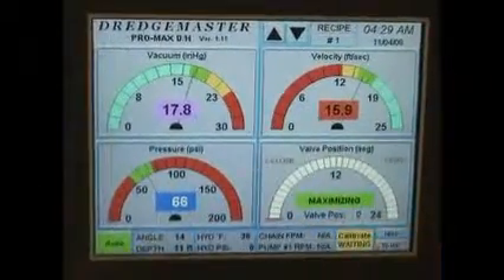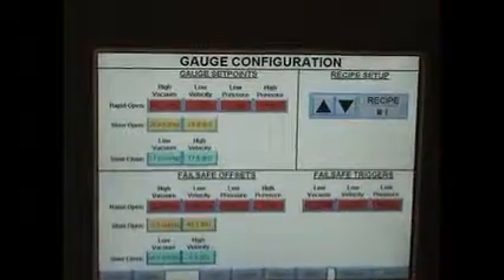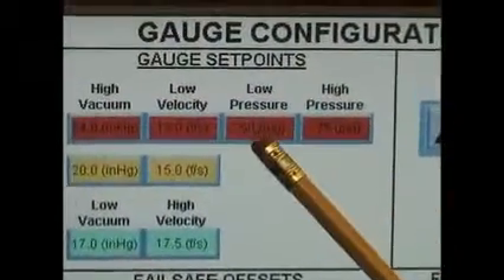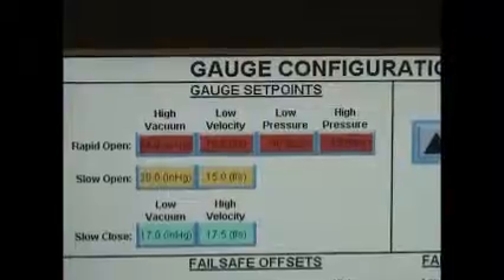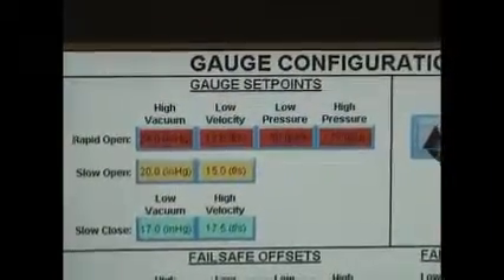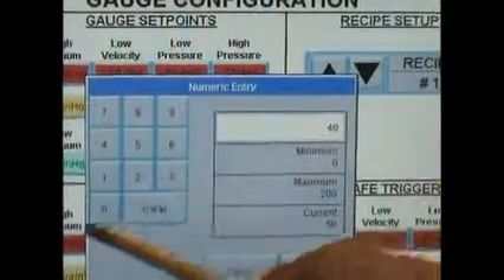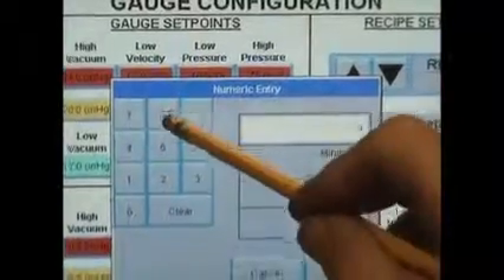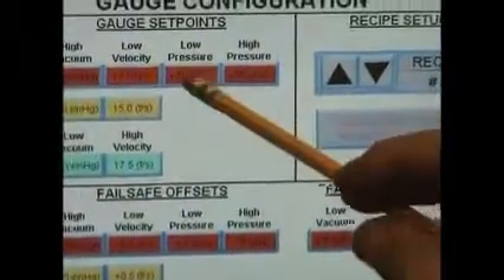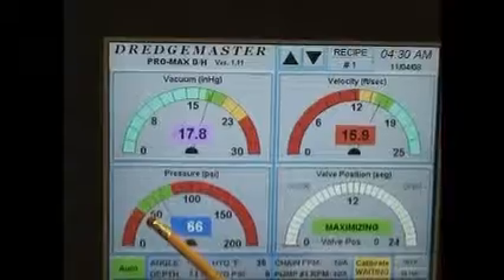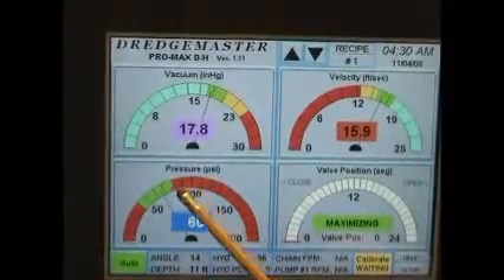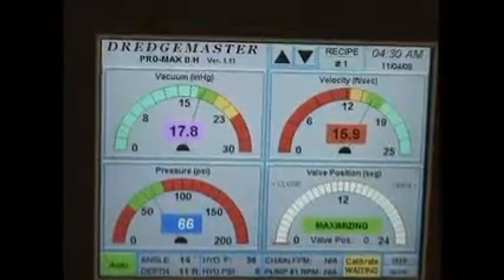To change our set points on the pressure gauge, go into the setup screen. Our low set point pressure is currently set at 50 psi, or could be in bars. Our high pressure set point is currently set at 75 psi, or could also be in bar. Let's say we want this to be 40 psi before we want that valve to rapidly open. We simply enter in 40, and we need to have a zone in here. Maybe we want this to be 80 for our high side. So now we have our 40/80 in there. Press to accept. Go back to our main screen. Now we can see it's going to be 40 before the valve opens up on the low side. It's going to be 80 before it opens up on the high side.